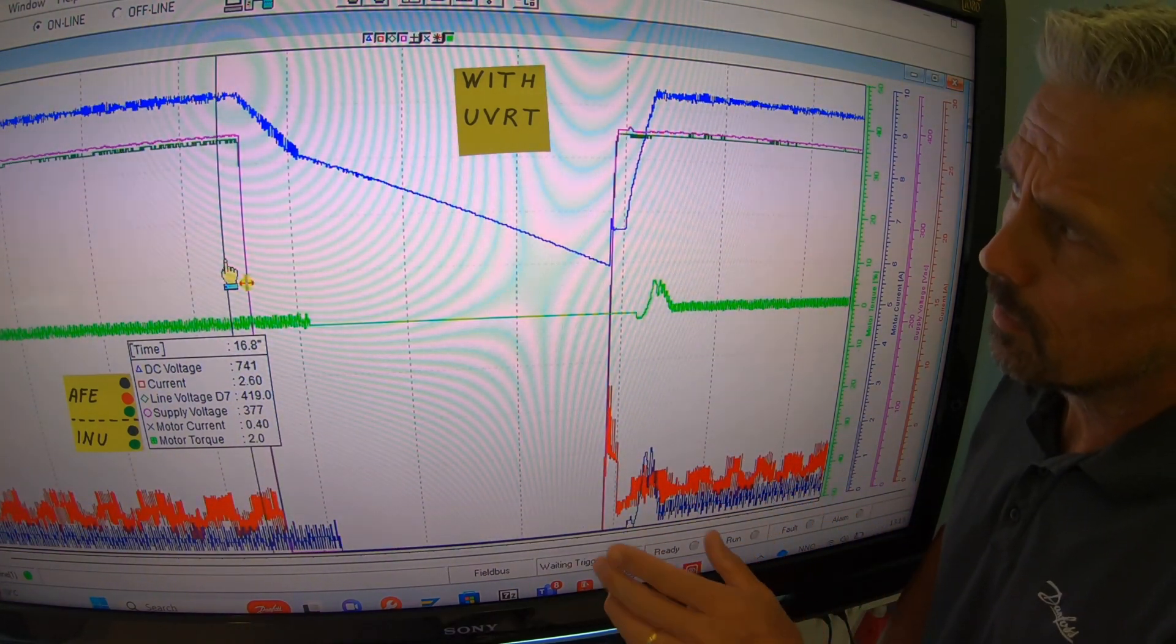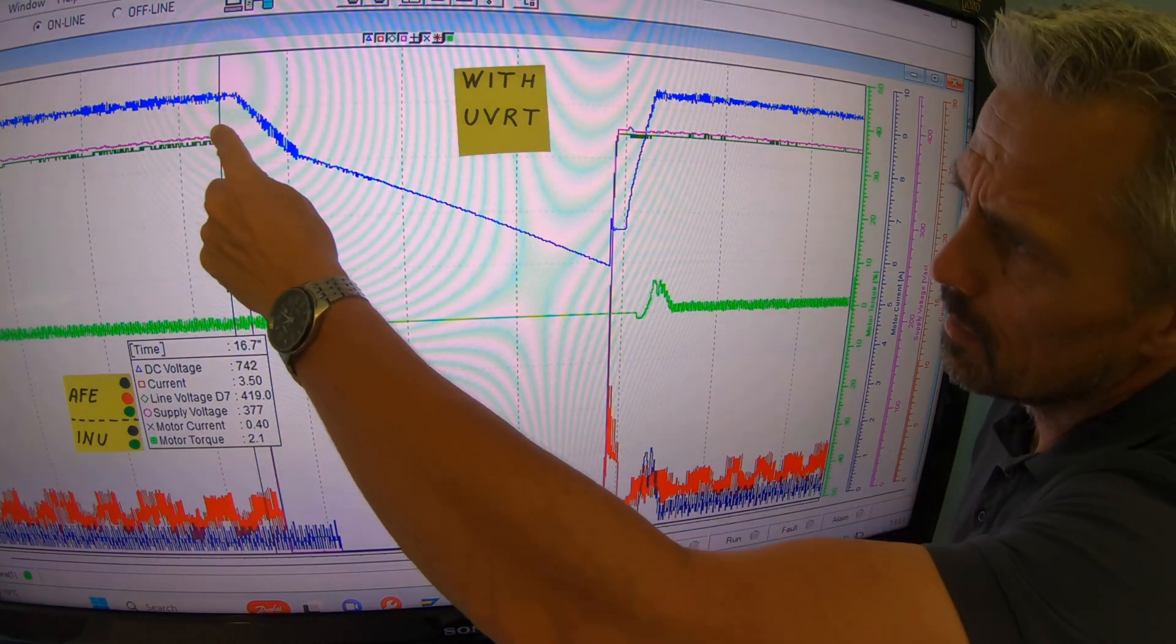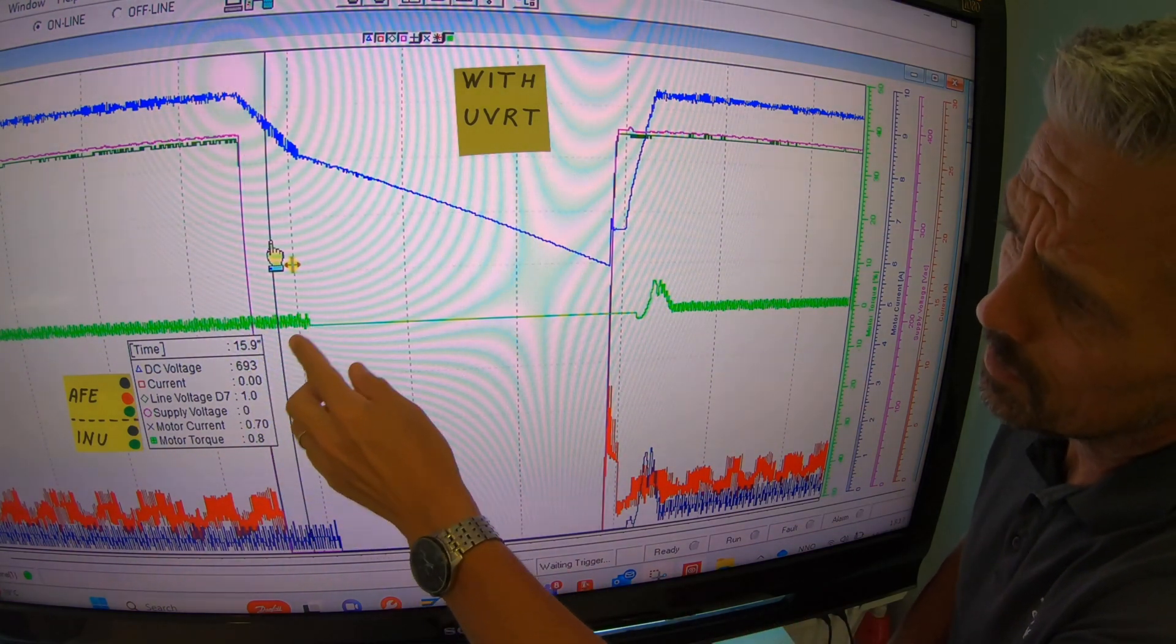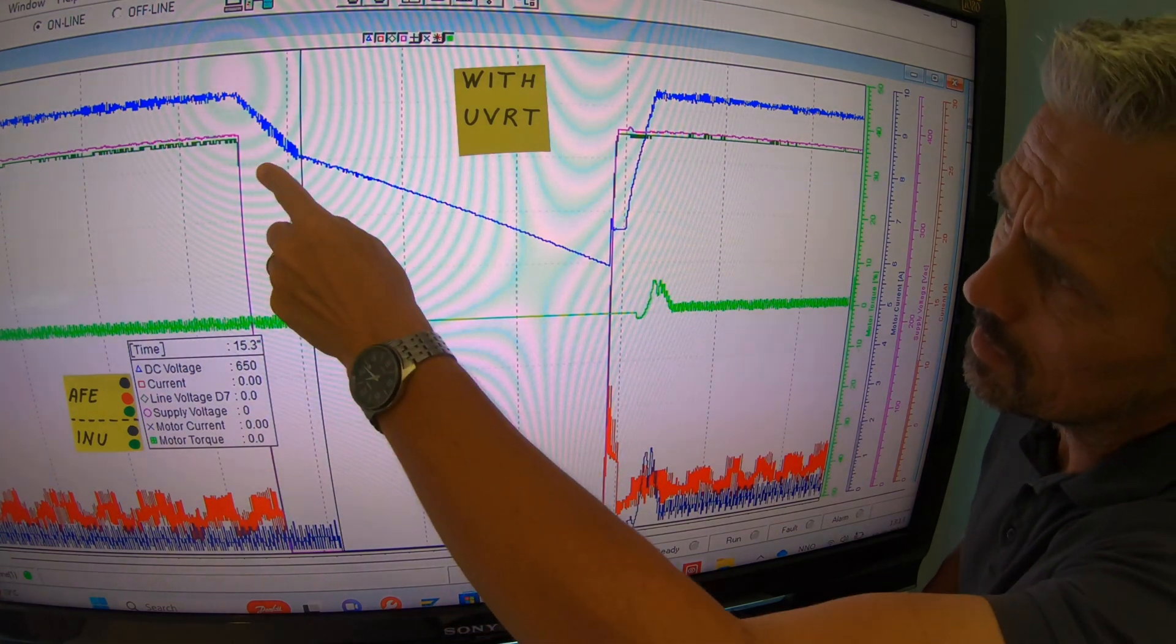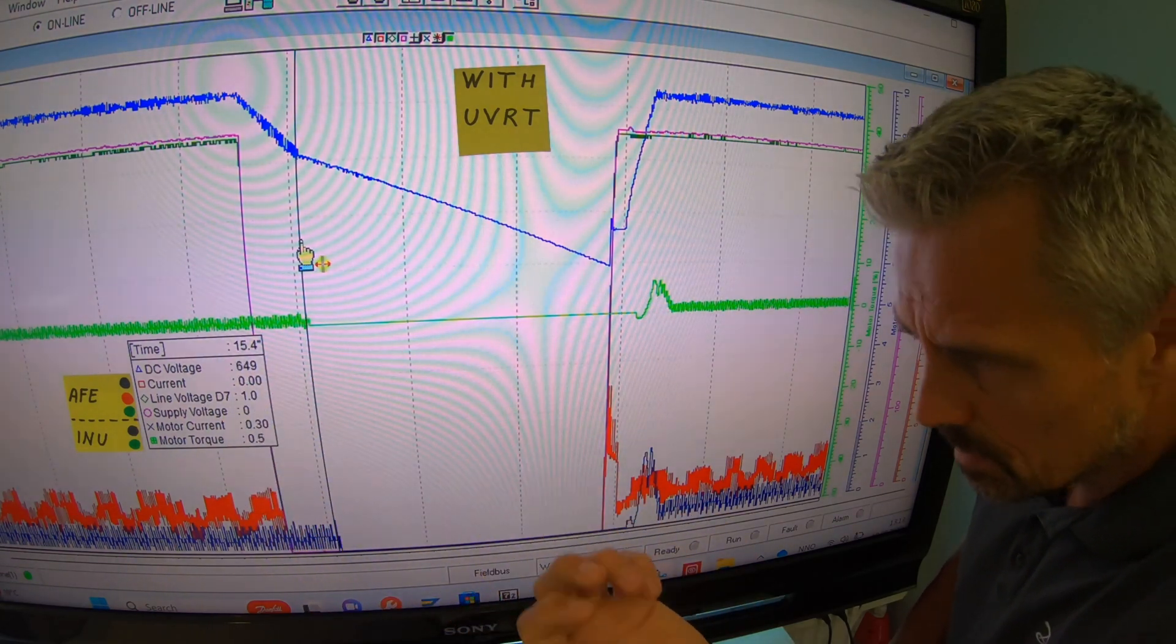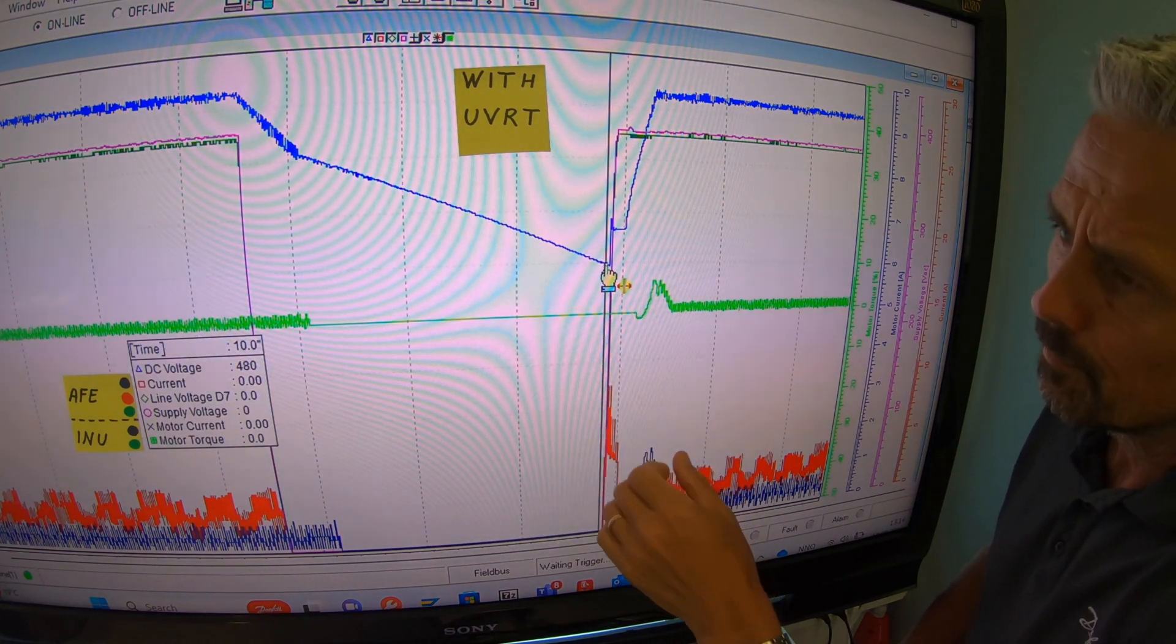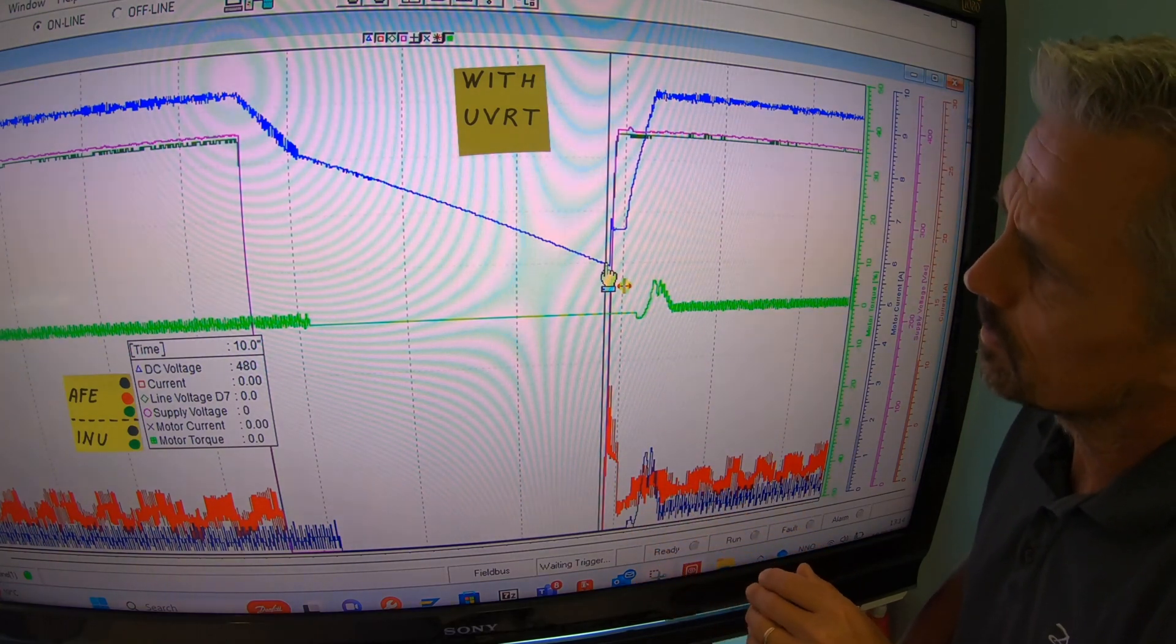This is the behavior with the undervoltage ride-through activated. We see that when the ship AC grid drops. The DC voltage is dropping and the consumers still extract energy, but only down to DC voltage level 650 volts, which we decided. Then it quits. Doesn't extract energy from the DC bus. Now we preserve the DC bus as long as possible. All the way down here. And still it is above trip level and the voltage to trip level of the drives.